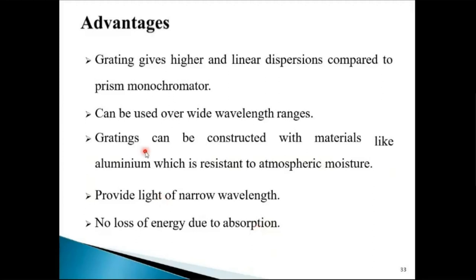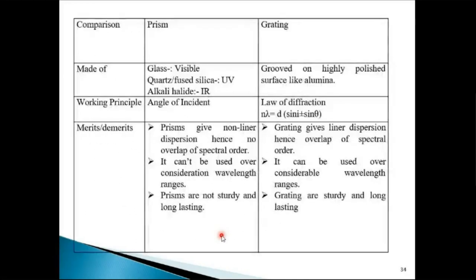Gratings give higher and linear dispersion compared to a prism monochromator. They can be used over a wide range of wavelengths. Gratings can be constructed with materials like aluminium, which is resistant to atmospheric moisture. They provide light of very narrow wavelength and, most importantly, there is no loss of energy due to absorption by the device itself.